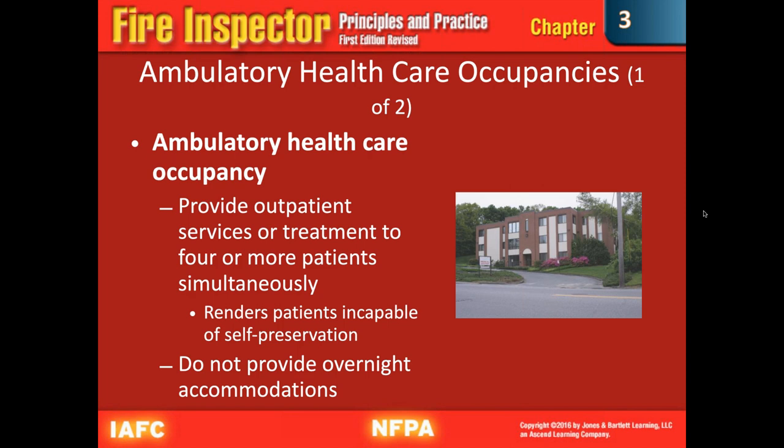Your personnel hopefully are doing drills to figure out how long it is going to take them to get everybody out of the building if it catches fire. Not everything has to be pull the fire alarm. Sometimes it can just be, here's a bed, nobody in it, but go put it in that far room at the end of the hallway. And then at some point today, I'm going to say the fire alarm went off and you have to go and get that bed out. See how long it takes you to move it, and then multiply that by however many beds you got on the floor. I mean, it could be tabletop stuff, whatever. But they need to be doing drills. That's something that you want to see when you talk to them.